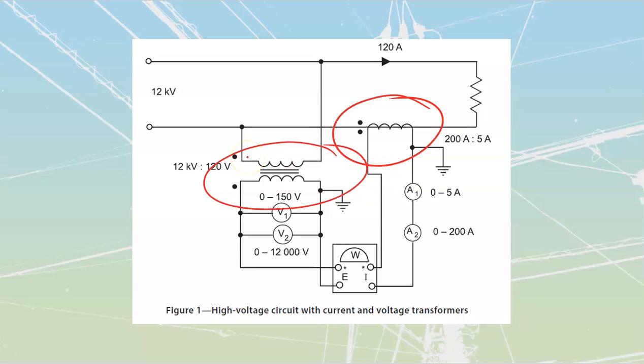This is all going to happen inside of a metering cabinet, but all we're going to be doing is, to their desired footprint sent by their designer, we're going to go and mount these things in, but we don't do any wiring connections. They take care of doing that all, because if we would go and do that improperly, we could end up with a meter that is going to be either blown up or running backwards. You could actually run the old analog meters backwards. I think that the new digital ones have now got unidirectional current sensing, so that's not a big issue anymore, but it was an issue previously. So what we need to do out of this learning task is we just need to be able to go and understand what the actual connections themselves are going to be.